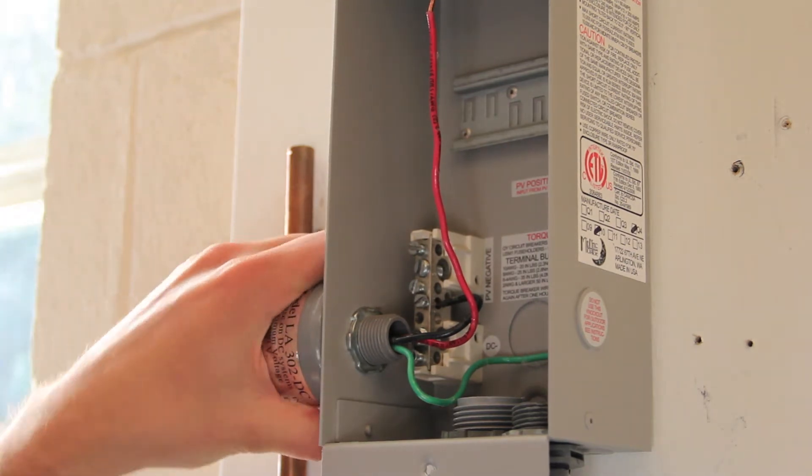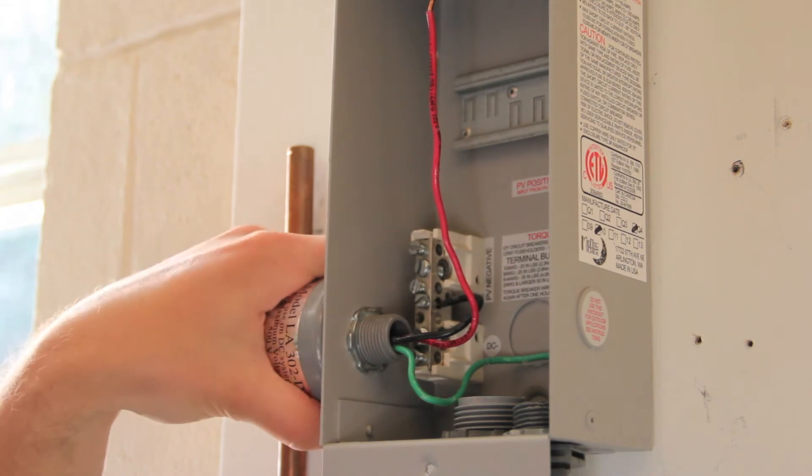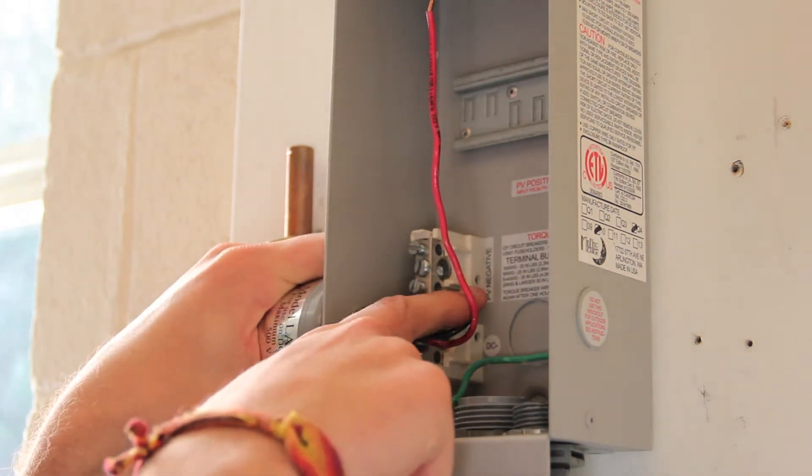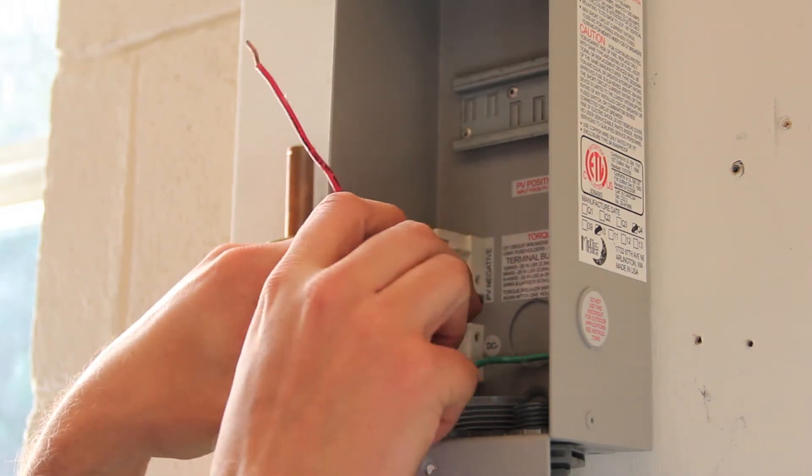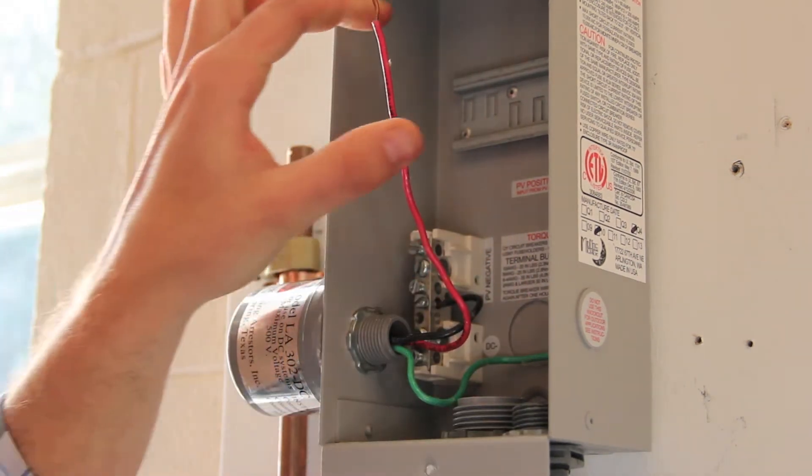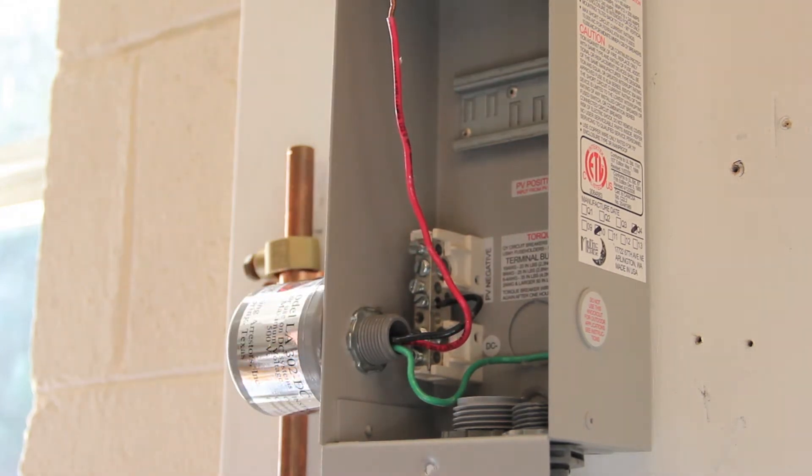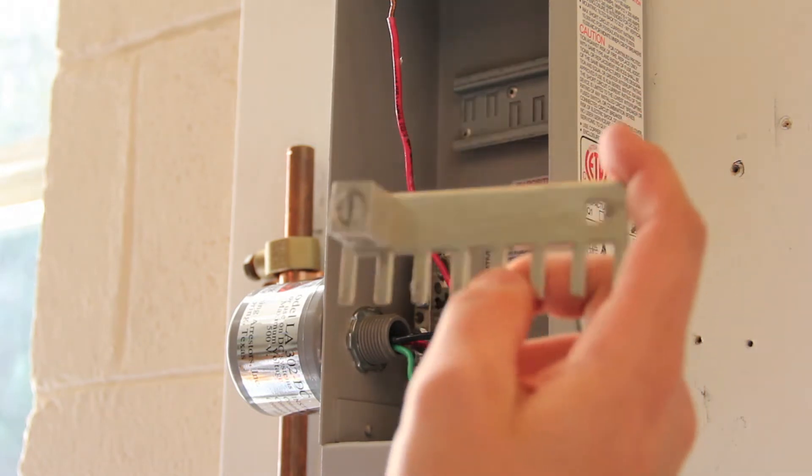I'm going to start wiring it up. I've already put a lightning arrester in this combiner box and landed the ground on the ground bus bar, the negative on the negative bus bar, and we still have our positive free here, which will be combined with two breakers here. One breaker for each photovoltaic string and a breaker combiner rail.